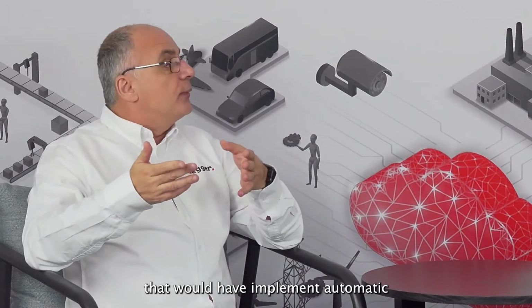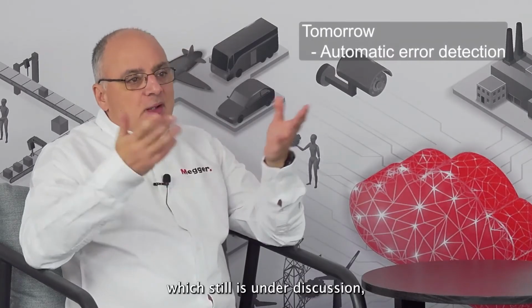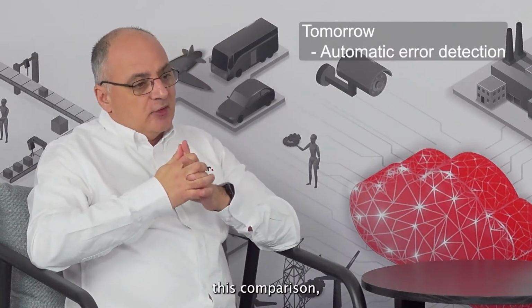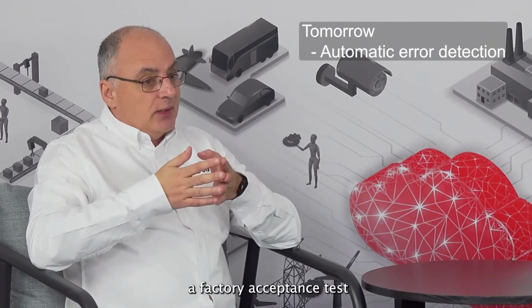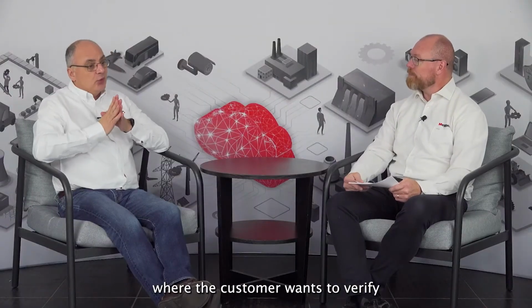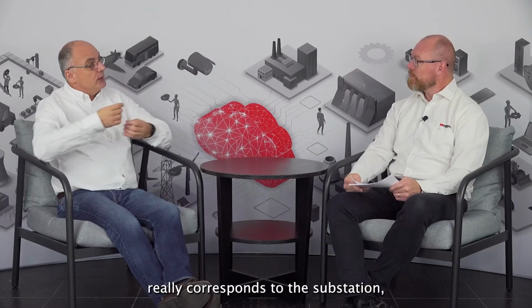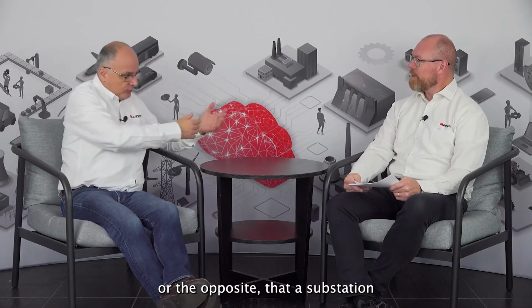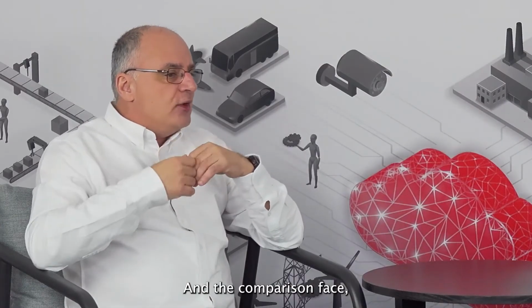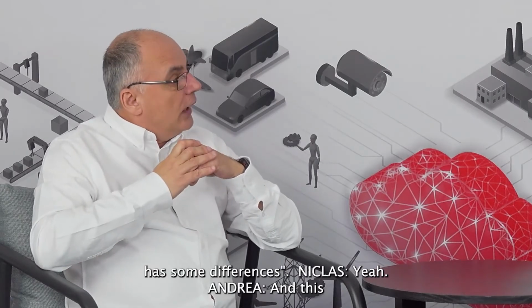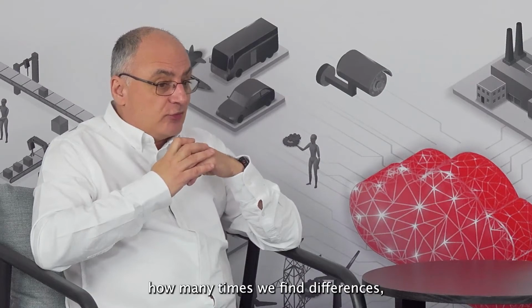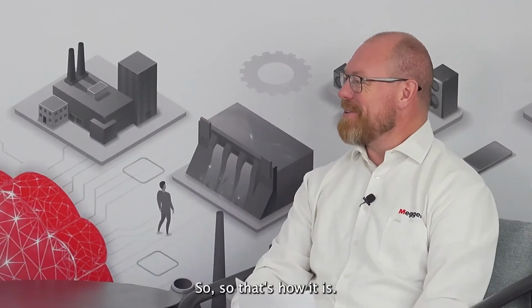If we could do it automatically, that would be implementing automatic maintenance routines, which is still under discussion. But we can do this comparison, for example, during the factory acceptance test, where the customer wants to verify that the SCD file given by the system integrator really corresponds to the substation, or the opposite, that the substation really corresponds to the SCD file. Depends on what you say. Normally we validate the SCD file, because we know the substation works, we are testing it, so we want to validate the SCD file. And if the comparison fails, you have some difference, you say, no, the SCD file has some differences. And how many times do we find differences? It's 100% of the times. So that's how it is.